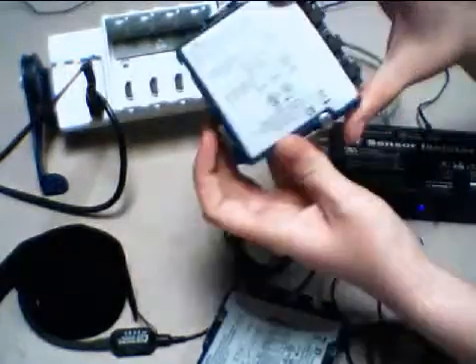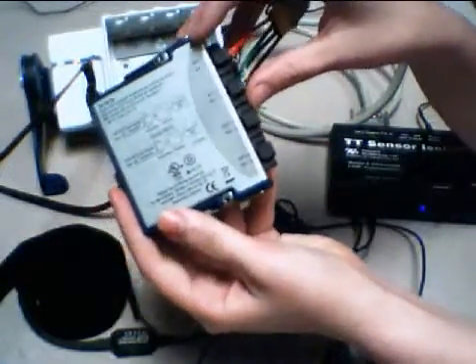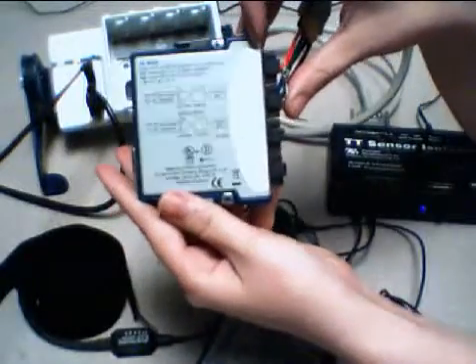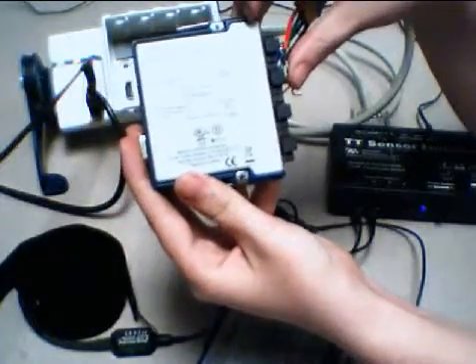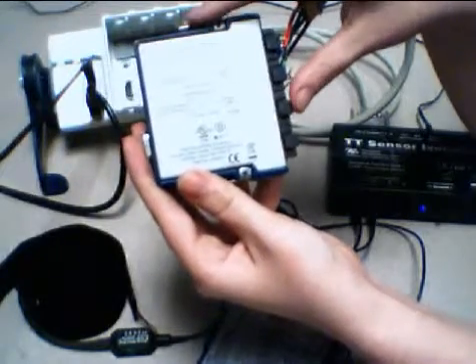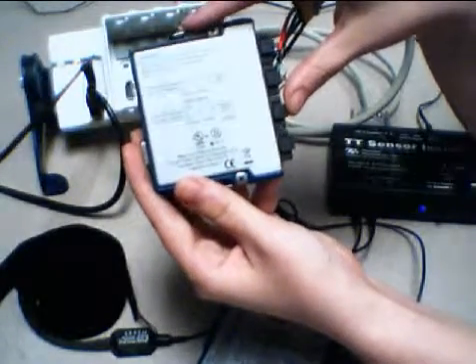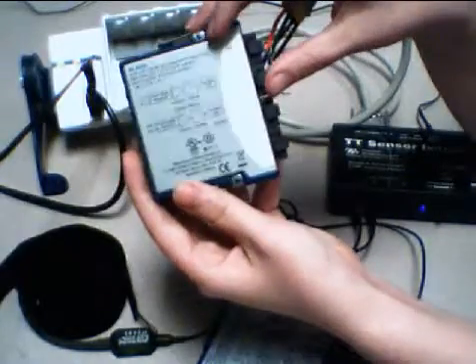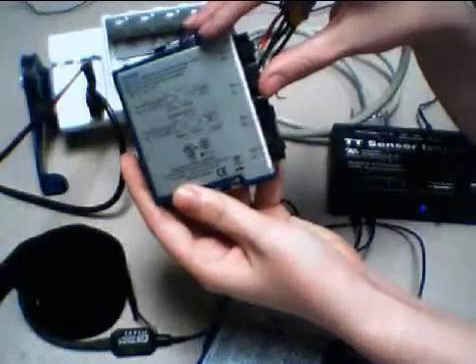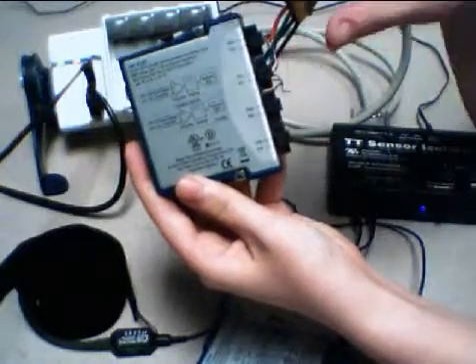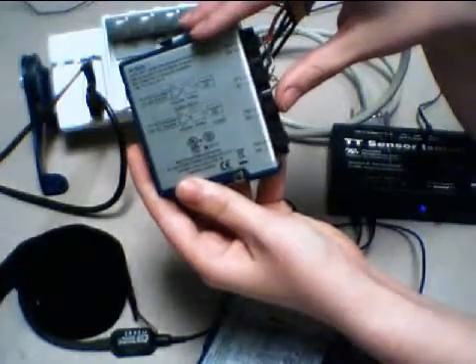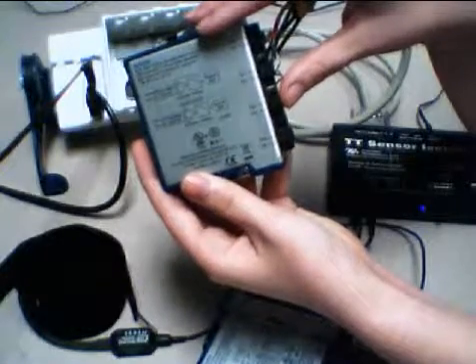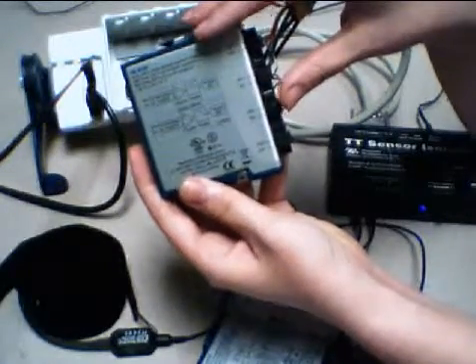Let's talk about that module. Here I have the 9239 and this is going to be the four channel, plus or minus 10 volt, 24 bit simultaneous analog input module. Basically, this module is going to be excellent for measuring dynamically varying voltages like those of interest in biomedical applications. The 24 bit ADC is very precise in how it measures relative changes.